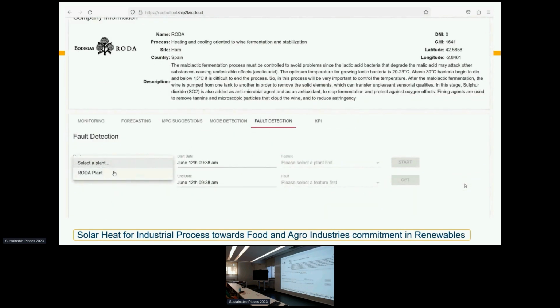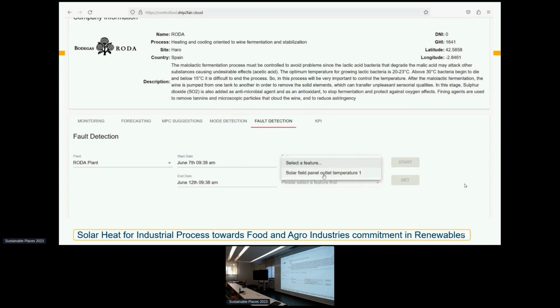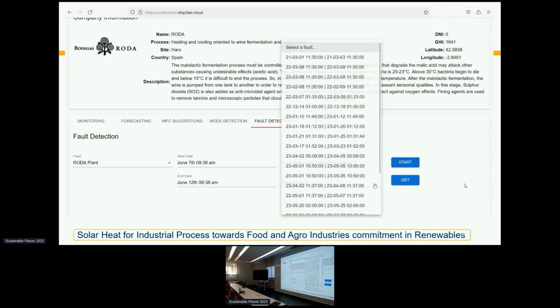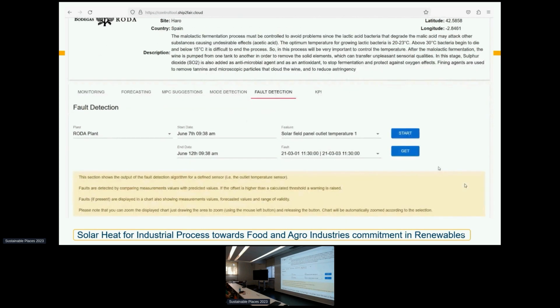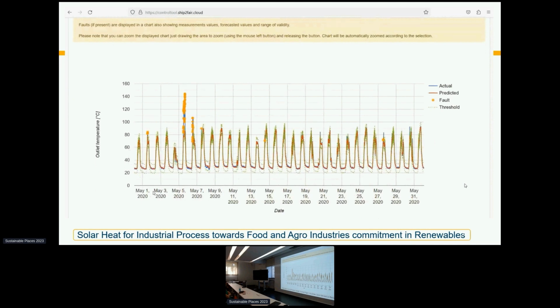Regarding fault detection, it is similar. You select your plant—typically process plant as well as solar thermal plant—and select a feature, for example the outlet temperature of your solar field, and a certain date. Then you click get, and you see the outlet temperature of the solar collector field, where these dotted lines characterize a fault. Here the algorithm found it faulty that it rises to such a high temperature, which is actually true, since the solar thermal field should not go up that high, and then you are informed.